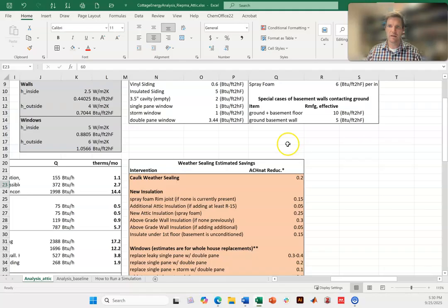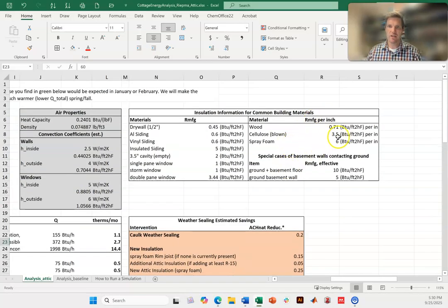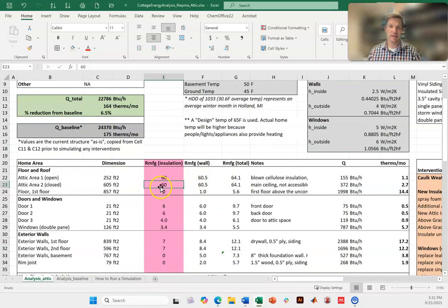If we look, cellulose insulation is about R3.5 per inch. So R60, we're talking about 18 inches of insulation, 1.5 feet thick. Even if we had spray foam, we need 10 inches of space to add that R60 insulation. So we may not just have, again, that physical space here. So what I'm going to do is estimate that we maybe have enough space for R16 or R19 insulation. That would be about a 6-inch cavity for insulation.